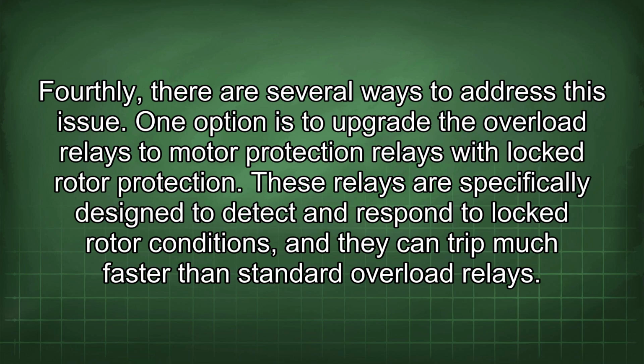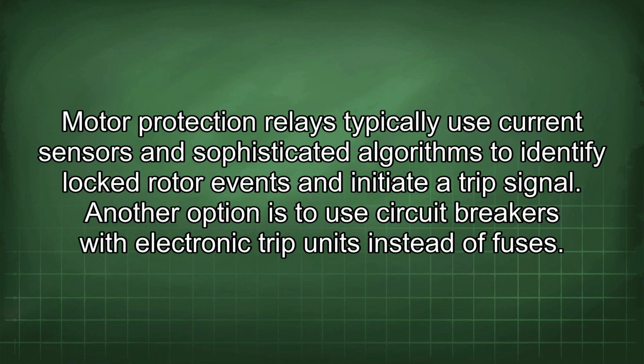One option is to upgrade the overload relays to motor protection relays with locked rotor protection. These relays are specifically designed to detect and respond to locked rotor conditions, and they can trip much faster than standard overload relays. Motor protection relays typically use current sensors and sophisticated algorithms to identify locked rotor events and initiate a trip signal. Another option is to use circuit breakers with electronic trip units instead of fuses.